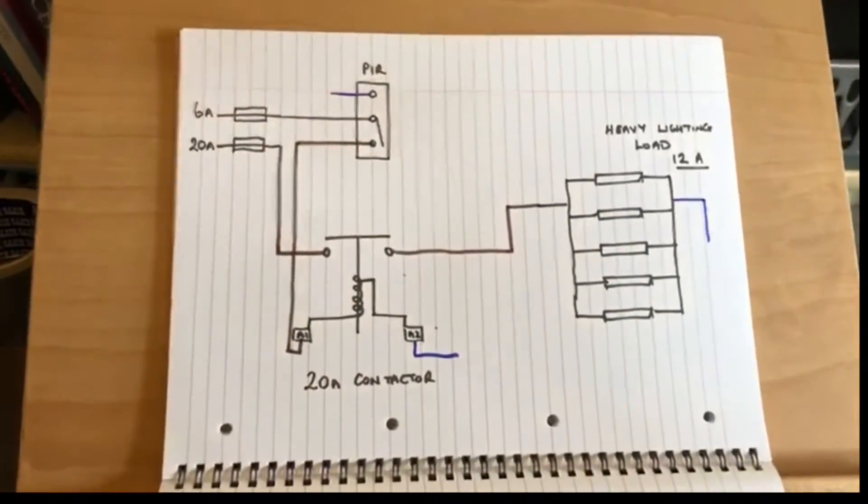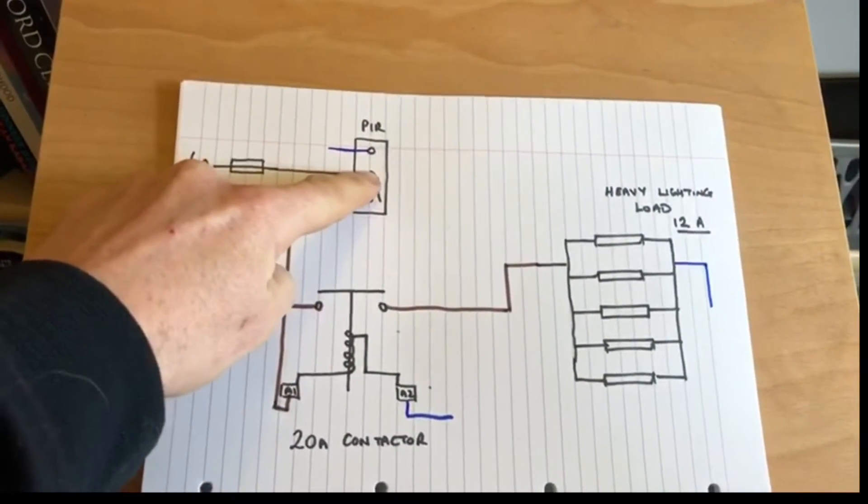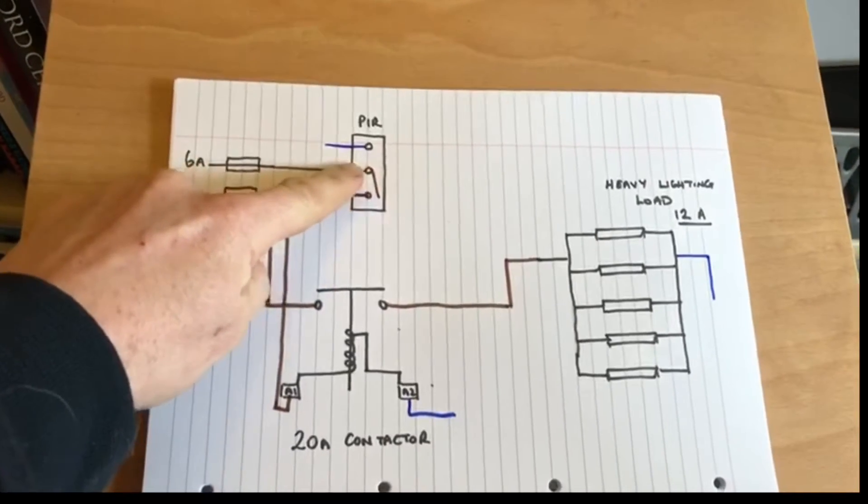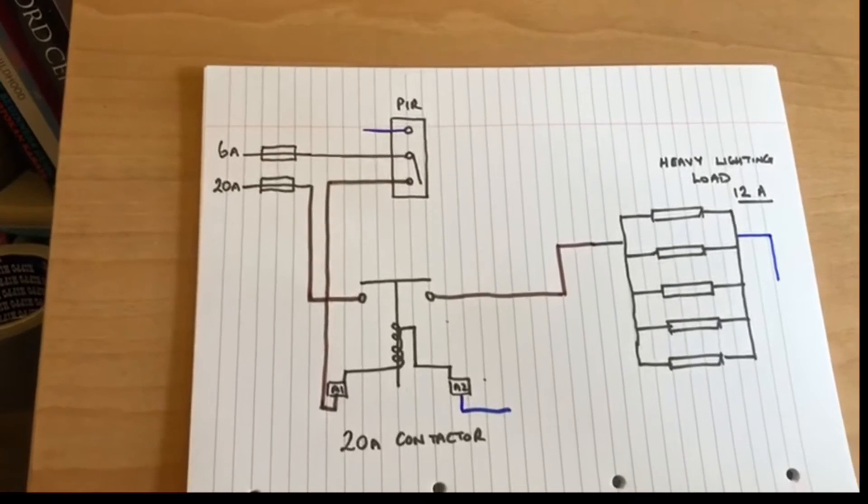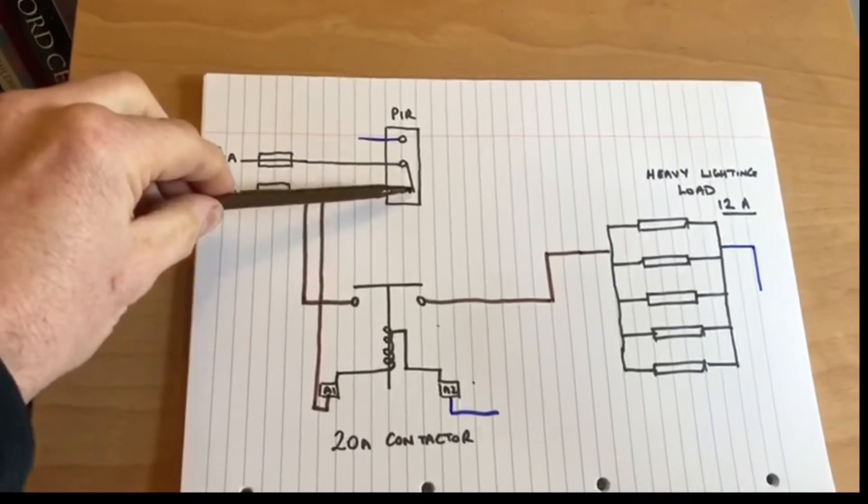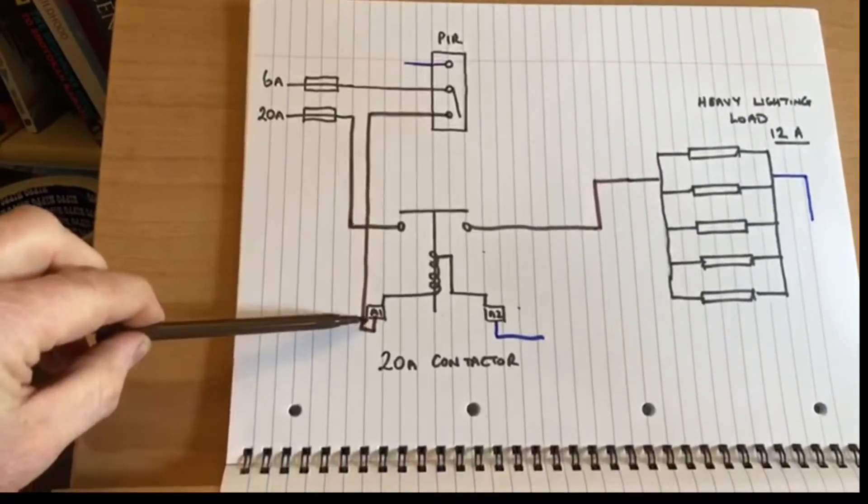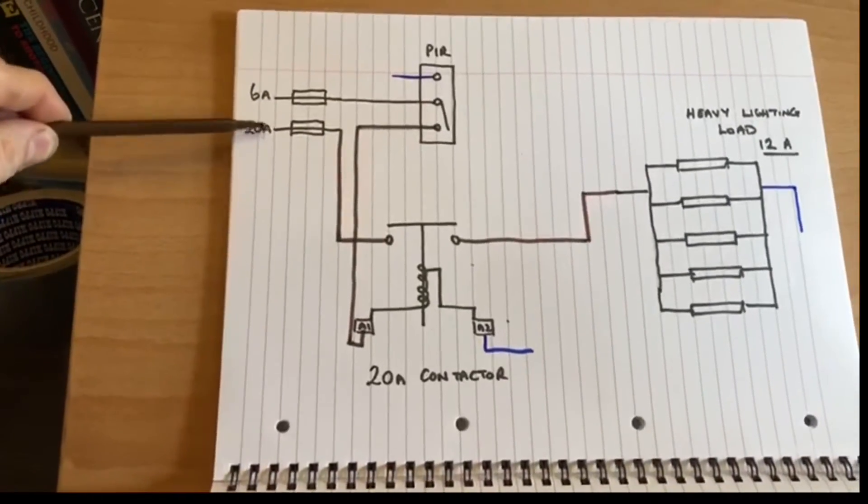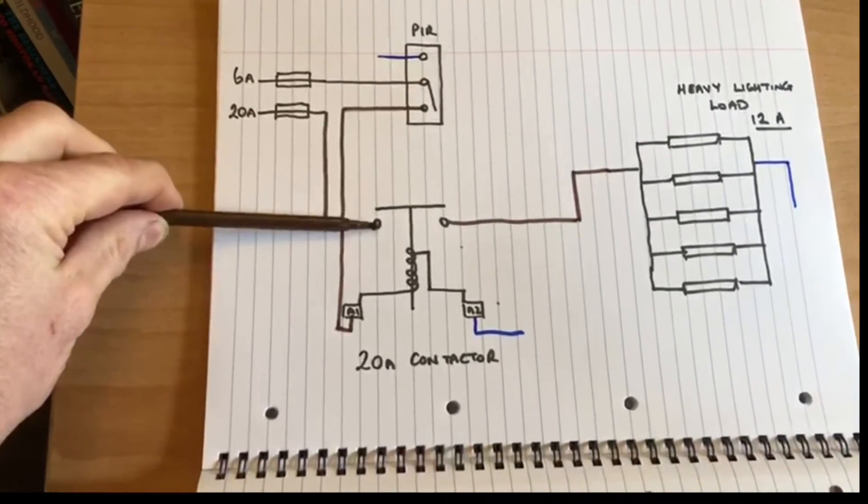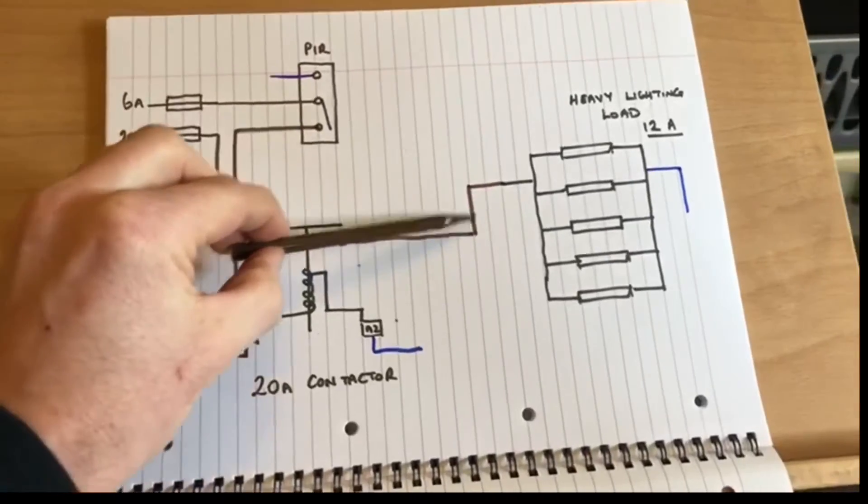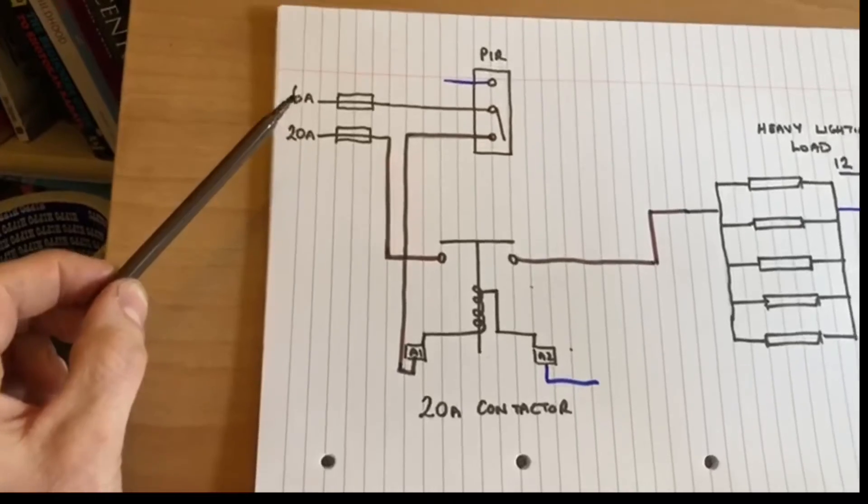So let's just run through how this is now going to work. We have our 6 amp feed coming through to the PIR, so again it's a permanent live position, a permanent live connection at the PIR. We then have from the switch outlet of the PIR that comes down to feed the coil. We then have our circuit breaker, a permanent live feed feeding the coil here and then feeding the bank of lights.